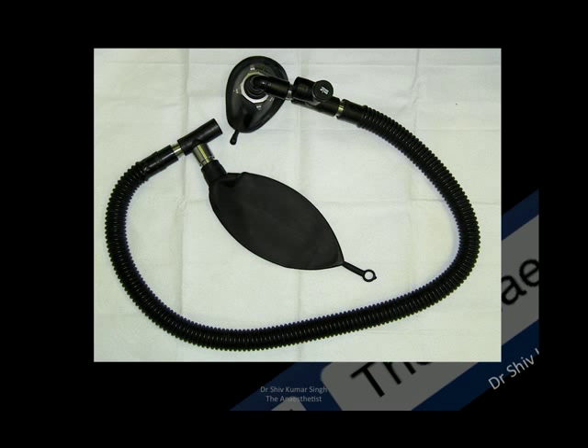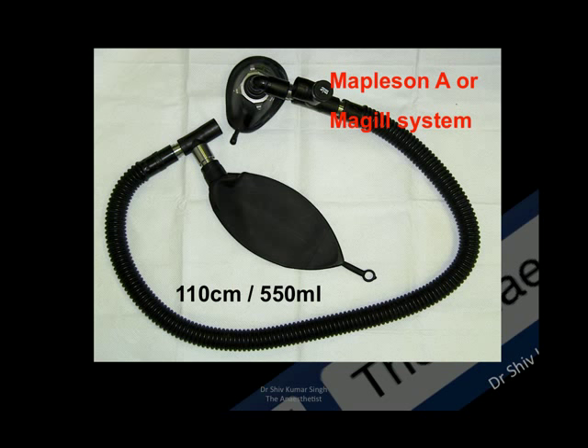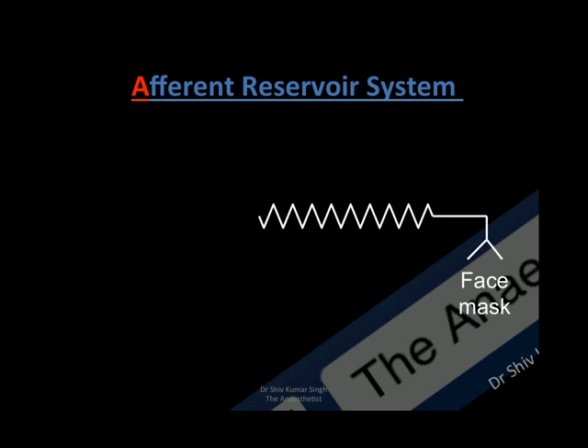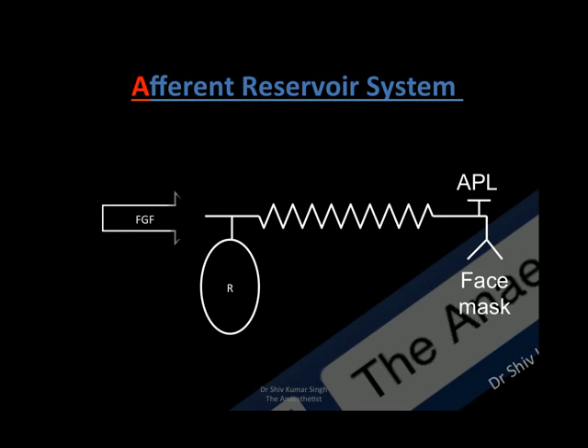Looking at the first of the Mapleson classification: the breathing system has a large breathing tubing with a capacity of 550 ml and a length of 110 centimeters. Mapleson classification of this system is A, but Miller classified it as an afferent reservoir system. The system has corrugated tubing, a face mask, APL valve, a reservoir bag, and fresh gas flows. The reservoir bag is actually very near to the fresh gas flow — that is the afferent limb, just like the afferent arterial side where blood flows in.